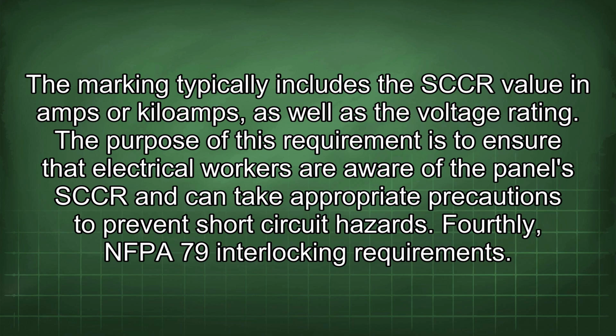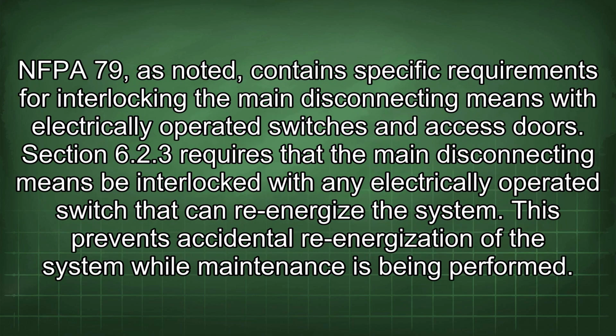Fourthly, NFPA 79 interlocking requirements. NFPA 79, as noted, contains specific requirements for interlocking the main disconnecting means with electrically operated switches and access doors. Section 6.2.3 requires that the main disconnecting means be interlocked with any electrically operated switch that can re-energize the system. This prevents accidental re-energization of the system while maintenance is being performed.